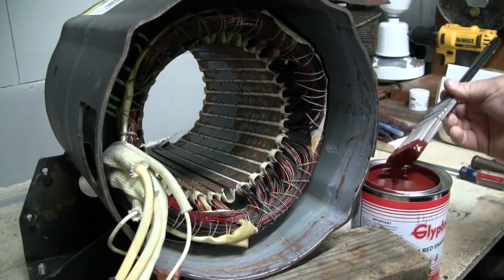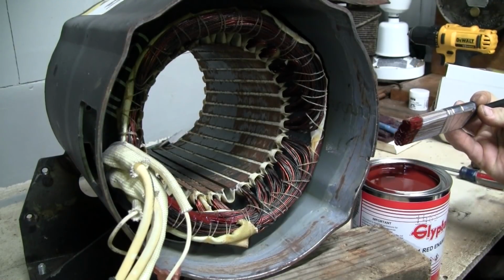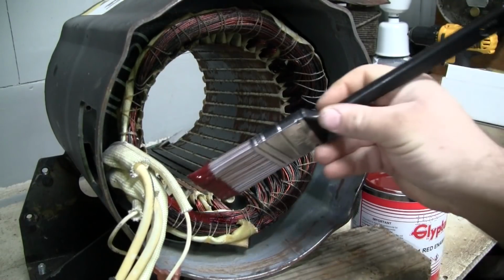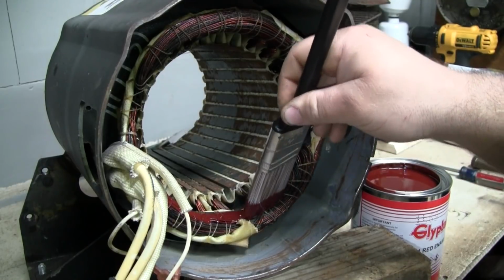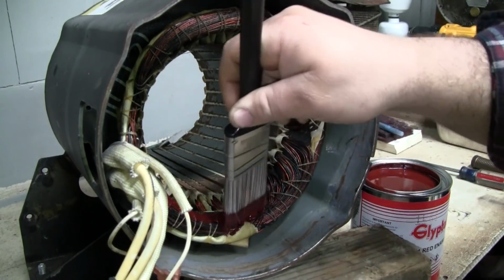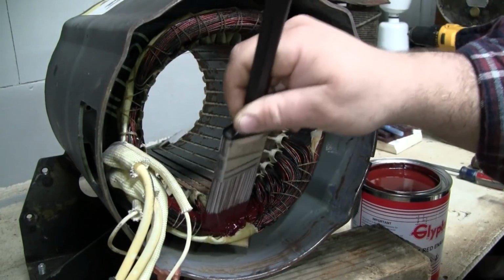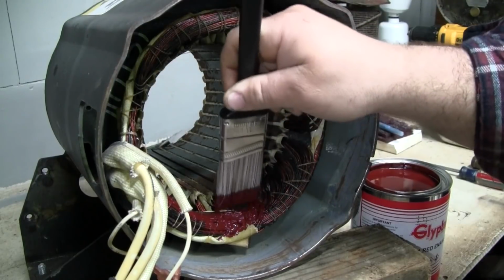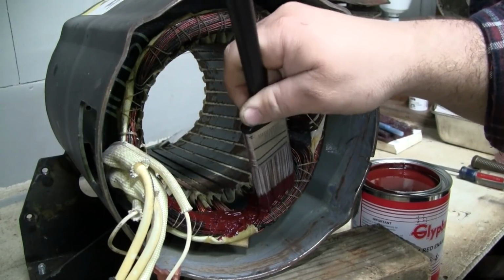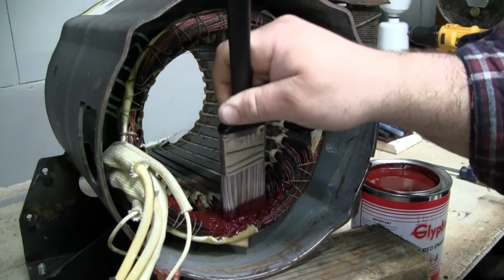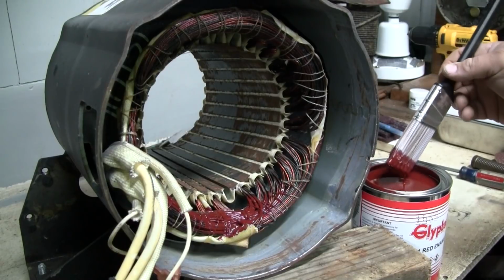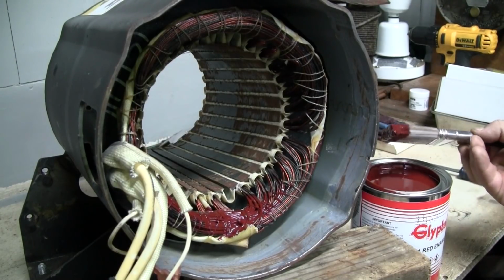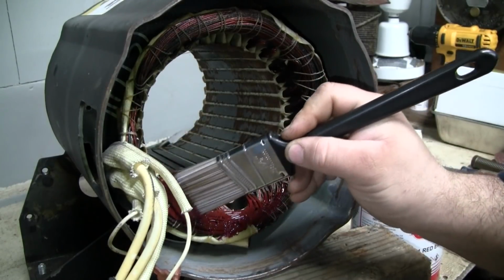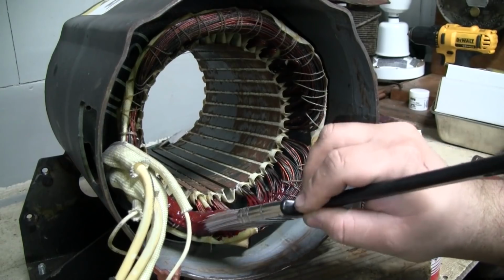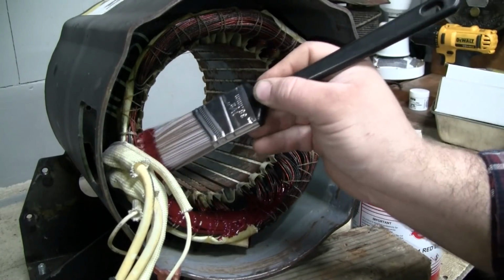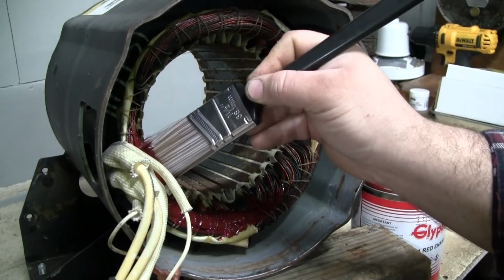Alright, I actually bought a new can of this stuff specifically for this job. So I'm just trying to dab it in on the windings. Kind of use the bristles of the brush to force it in the crevices between the windings. If any of it drips down on the frame, I'm not concerned. It's fairly thick, about as thick as a regular oil-based paint. Tends to stay where you put it, more or less. It helps that I just had the heater running, so everything is up to temperature here. It's probably about 75 degrees in here right now.